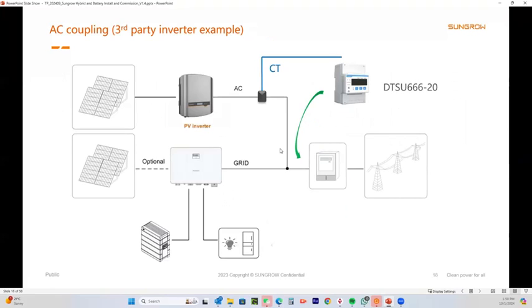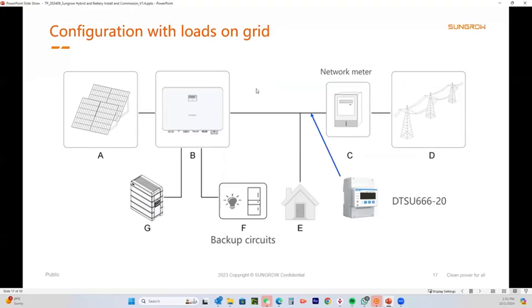Another time you will need to put that meter on is if there is a third-party inverter, AC coupled. You install the meter and you put channel 2 CTs on the output of that. There is a separate training module for the meter and documentation for the meter. I'm not going to go into it in too much detail on this one here, but I do suggest you do that training as well. Now, if you look at this diagram here, it does say panels optional. This is to do with AC and or DC coupling. I'm going to go back a slide to here, just to explain what AC and DC coupling is.